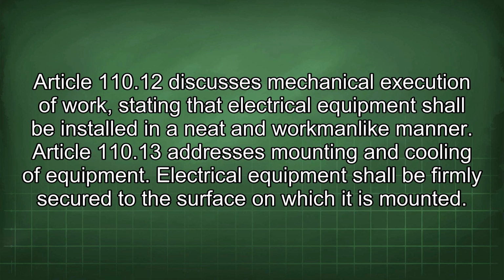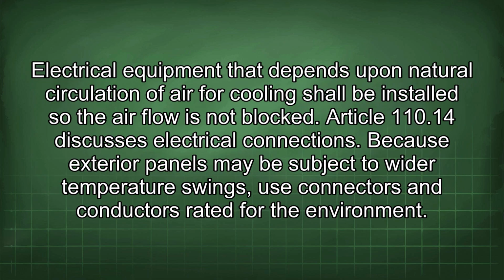Article 110.12 discusses mechanical execution of work, stating that electrical equipment shall be installed in a neat and workmanlike manner. Article 110.13 addresses mounting and cooling of equipment. Electrical equipment shall be firmly secured to the surface on which it is mounted. The electrical equipment that depends upon natural circulation of air for cooling shall be installed so the airflow is not blocked.